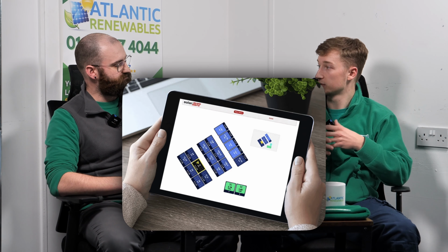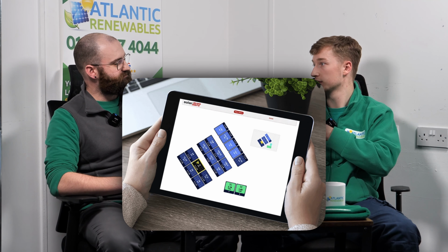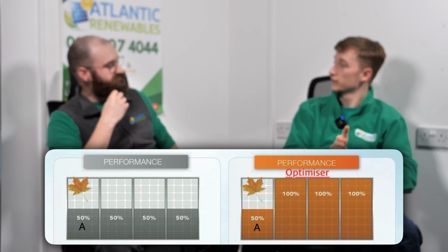So there are the benefits with the monitoring. You can see what every single panel is doing at any given time, and as you say, the panels are connected in parallel now rather than in series in a big string. So they work on their own. If panel A was working at 50% efficiency due to a shadow from a tree, the one next to it would still work at 100% if that was clear of the shade. If you didn't have the optimizers, all the panels in that string would drop because they're all connected in series. So that's what we look at if there is a shading problem.